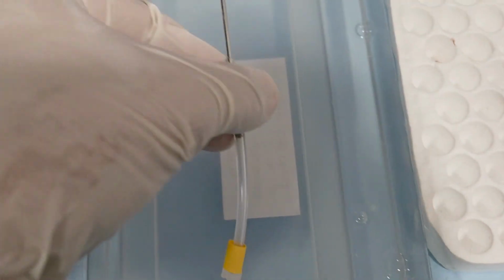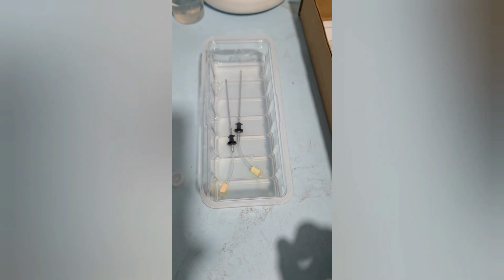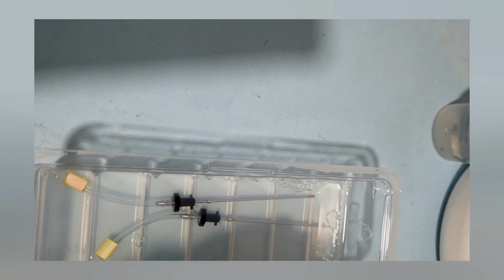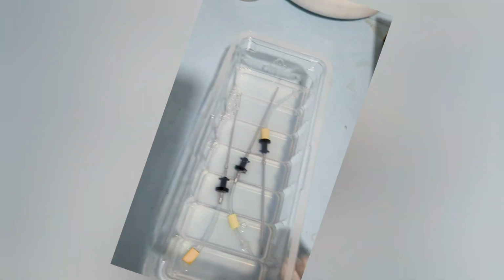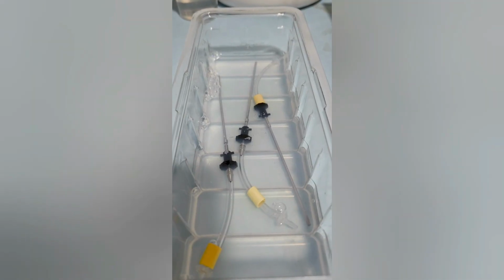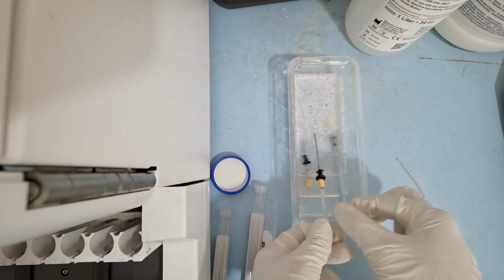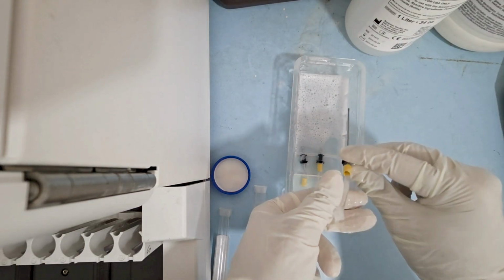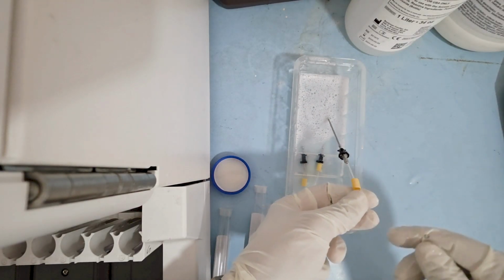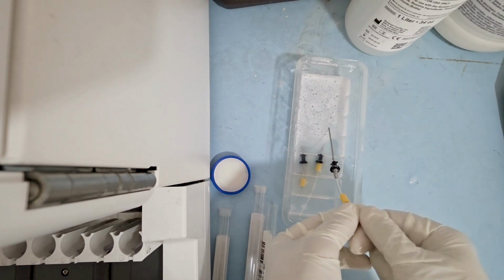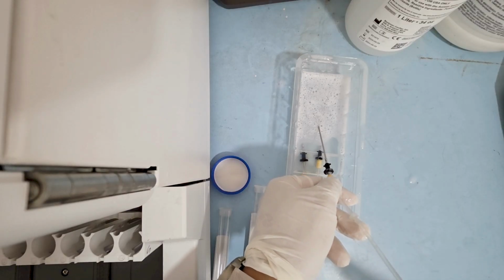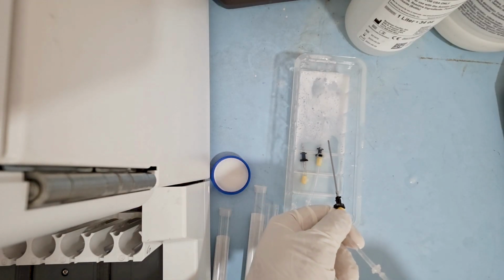Now we'll move on to the second stage, which involves cleaning the previously used aspiration probes that we just removed. To begin cleaning, we immerse the used probes in a contrad cleaning solution for approximately 30 minutes. This soaking step helps to loosen and dissolve any dry protein residues or debris inside the probes. After the soaking period, we start flushing the probes using the same solution to remove any remaining contaminants. Each probe is flushed 3 times to ensure that all internal pathways are completely clean and unobstructed.